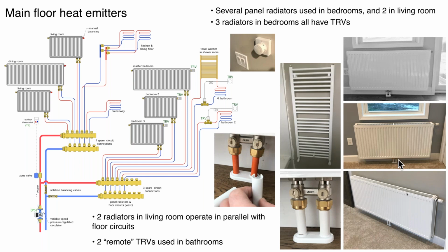Here are some examples of those panel radiators. You see 2-inch on center tubing right up through the floor, double isolation valve, and right up into the bottom of the panel. Okay. These over here, these panel rads and floor circuits are combined back to a common manifold. And the flow to that manifold is all controlled through a single zone valve by a thermostat. So that's a good example of mixed emitters. These are all going to get the same water temperature. All right, so they were sized with that in mind.